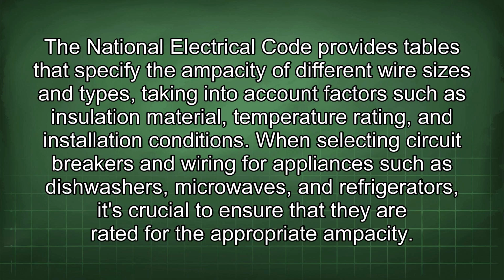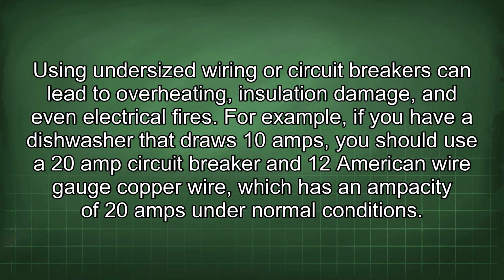The National Electrical Code provides tables that specify the ampacity of different wire sizes and types, taking into account factors such as insulation material, temperature rating, and installation conditions. When selecting circuit breakers and wiring for appliances such as dishwashers, microwaves, and refrigerators, it's crucial to ensure that they are rated for the appropriate ampacity. Using undersized wiring or circuit breakers can lead to overheating, insulation damage, and even electrical fires.